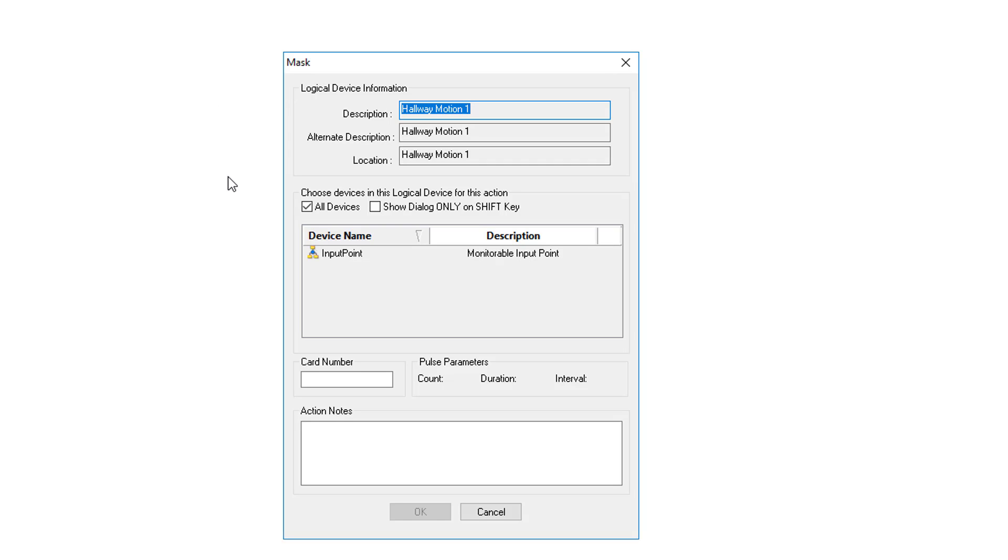The difference between mask and timed mask is the timed mask will automatically unmask itself when the timer expires. The mask has to be manually unmasked. So as you see we do not have a time period over here. We're just going to mask it and it's going to stay masked until it's unmasked or re-enabled.